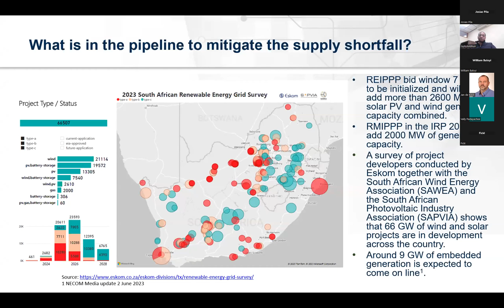We ask that there be a coordinated effort in adding this capacity online. Our system operator, together with grid planners, need to determine whether the moment of inertia for the system is within an acceptable threshold, and if it's below that, whether there's sufficient mechanism to arrest frequency deviations resulting from a much lower nadir caused by integrating significant renewables into the system. We're not opposed to this happening, but it's important that adding this capacity doesn't cause operational issues, which requires a strong coordinated effort.